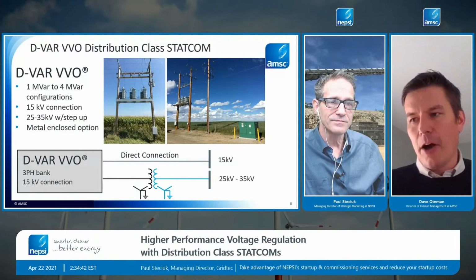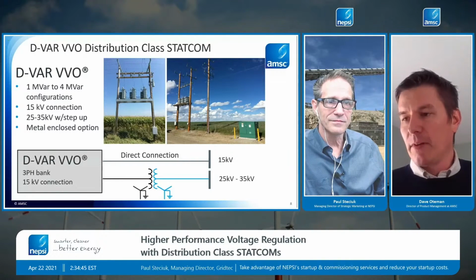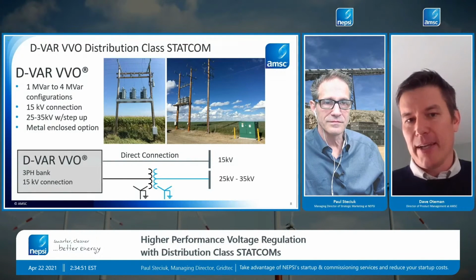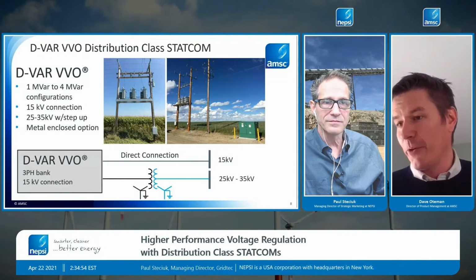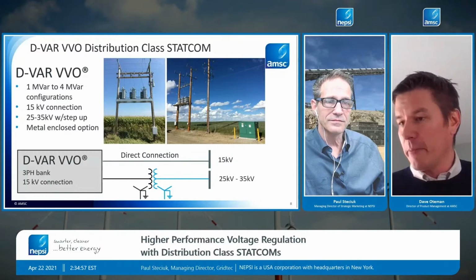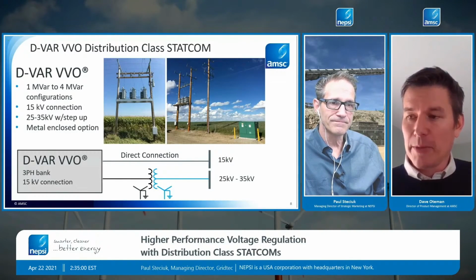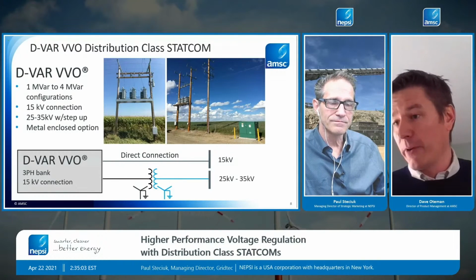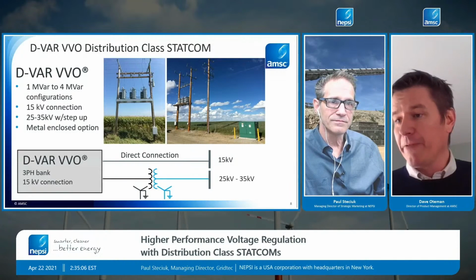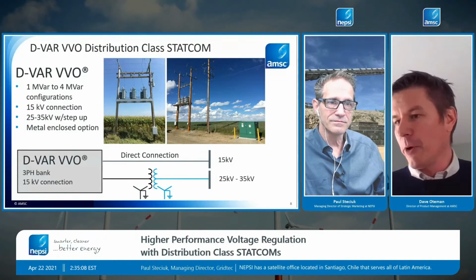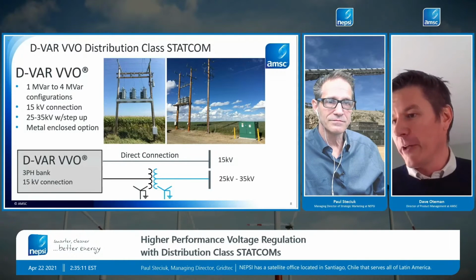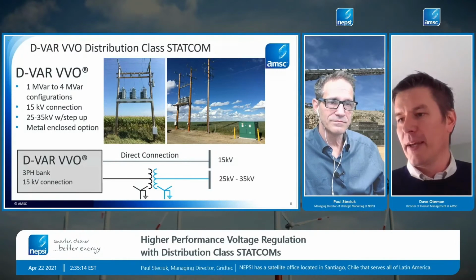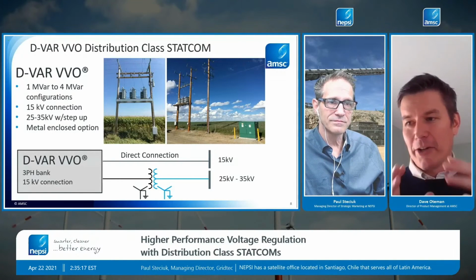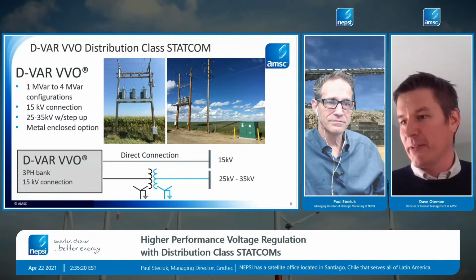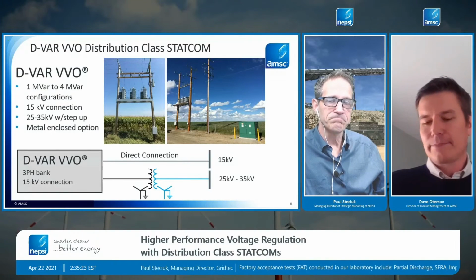In all these installations, each phase operates independently. For example, phase A can be fully inductive while phase B is fully capacitive if needed to balance the voltage. The system can also operate only in positive sequence mode if desired. By default we're in that independent mode, but for motor starting it's often appropriate to be in positive sequence mode. In our SCADA settings, you just set it to positive sequence and it won't do the unbalanced thing.